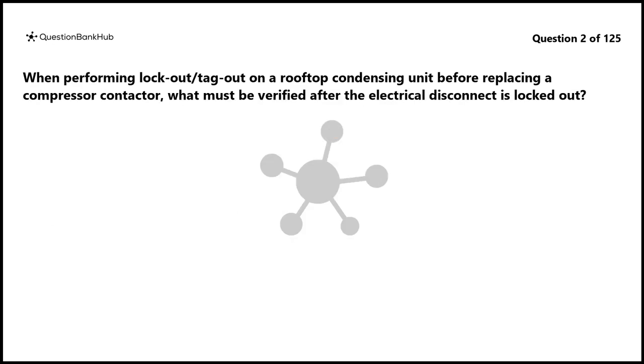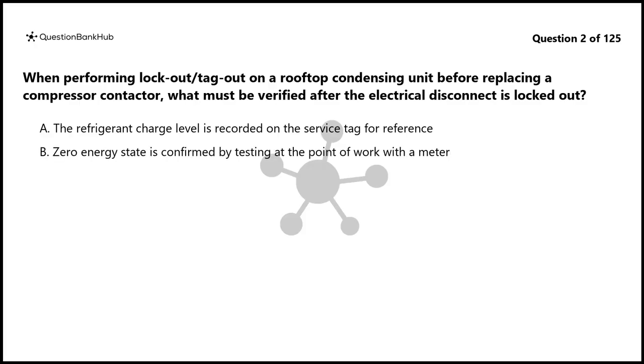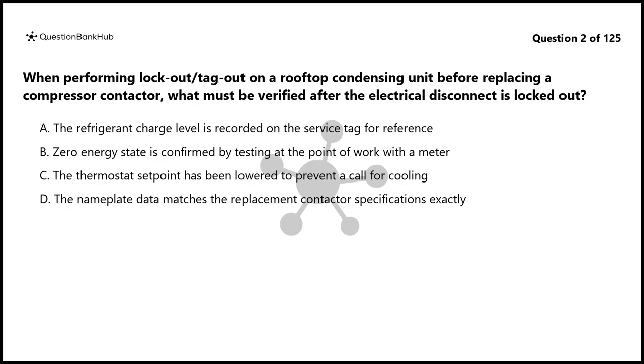Question 2. When performing lockout-tagout on a rooftop condensing unit before replacing a compressor contactor, what must be verified after the electrical disconnect is locked out? A. The refrigerant charge level is recorded on the service tag for reference. B. Zero energy state is confirmed by testing at the point of work with a meter. C. The thermostat setpoint has been lowered to prevent a call for cooling. D. The nameplate data matches the replacement contactor specifications exactly.